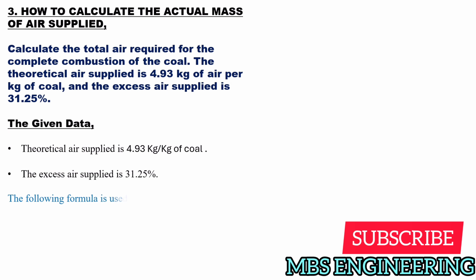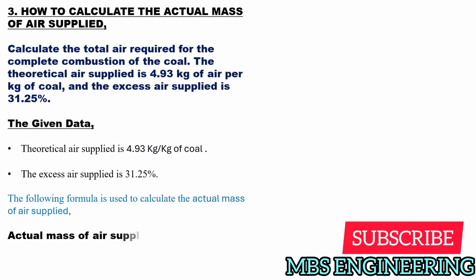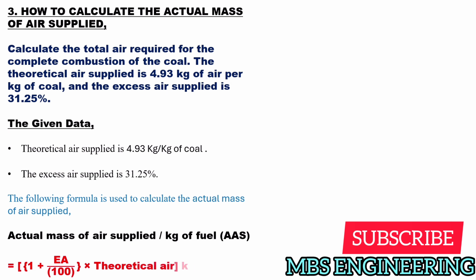The following formula is used to calculate the actual mass of air supplied. Actual mass of air supplied, kilogram per kilogram of fuel, AAS, is equal to 1 plus excess air supplied EA divided by 100, and then the obtained value is multiplied by theoretical air supplied.